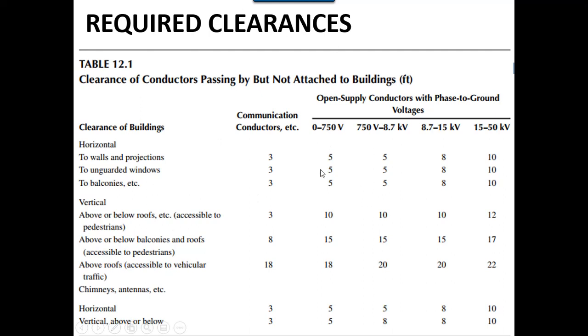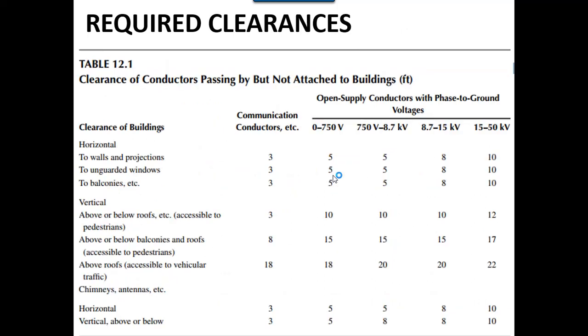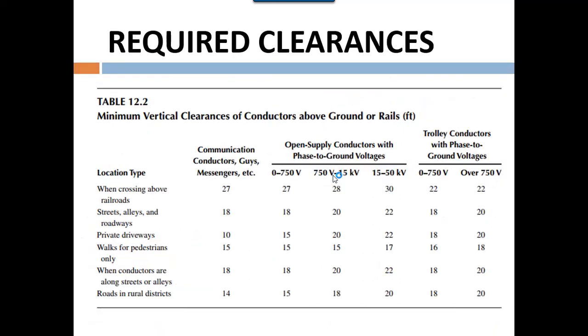There are tables showing horizontal and vertical clearance values in feet. For a voltage of 0 to 750 volts, the clearance to a wall or projection should be at least 5 feet, and for unguarded windows to balconies, values vary. Vertical clearance values change gradually according to requirements. For the minimum vertical clearance of the conductor above ground or rail at 0 to 750 volts, the required clearance is 27 feet.